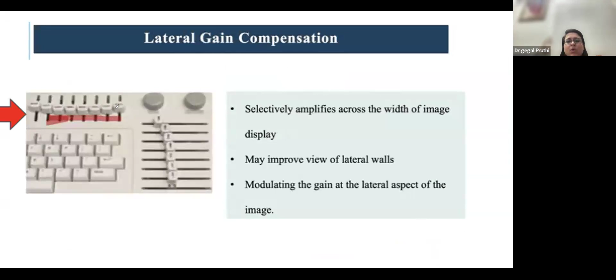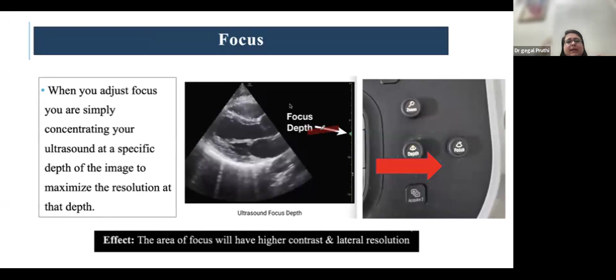Coming to the focus. When you focus, you are simply concentrating your ultrasound beams at a specific depth. So you are concentrating your ultrasound at a specific depth of the image to maximize the resolution at depth. As we know, as the beam propagates, it will diverge and lose lateral resolution. That is why we should use focus at the area of interest, because focusing narrows the beam and therefore you will have better lateral resolution at that depth.